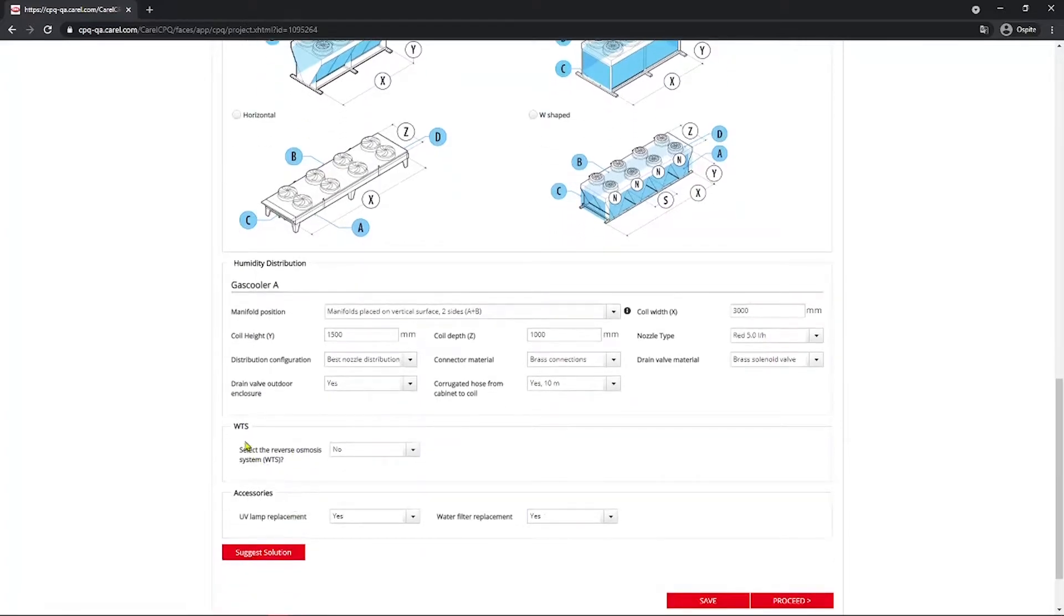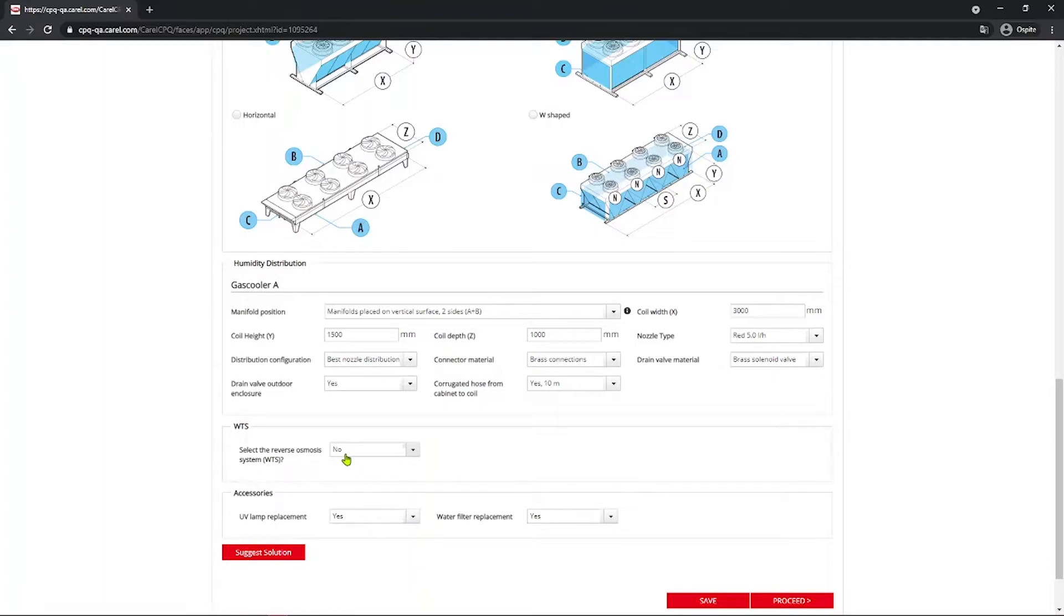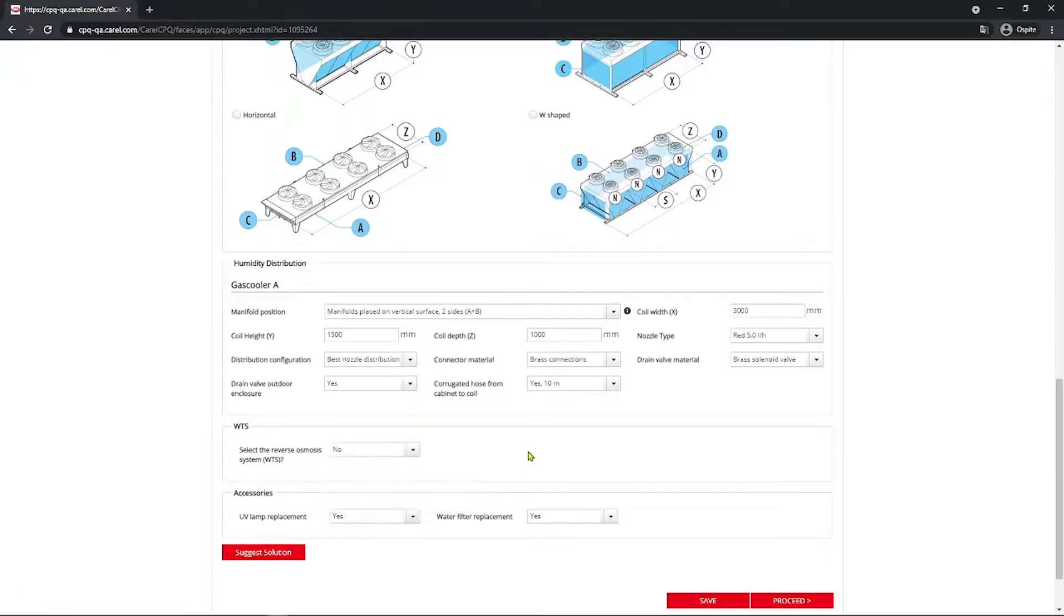The WTS selection. Using the demineralized water has the advantage of preventing the formation of lime scale on the coil. However, it's also important to underline that this type of water can be aggressive to the fins. So always remember to check compatibility with the customer if you want to go with the demineralized water. So that's why the default value is no, and we stay with no. But if you want you can size the WTS for one system or for more than one system if you have.